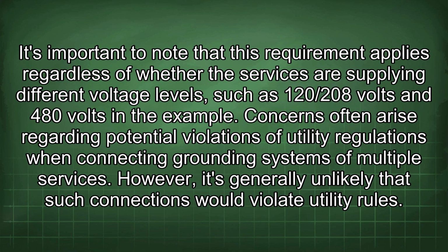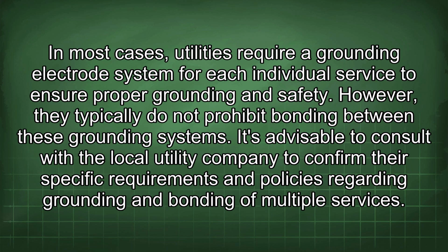Concerns often arise regarding potential violations of utility regulations when connecting grounding systems of multiple services. However, it's generally unlikely that such connections would violate utility rules. In most cases, utilities require a grounding electrode system for each individual service to ensure proper grounding and safety. However, they typically do not prohibit bonding between these grounding systems.